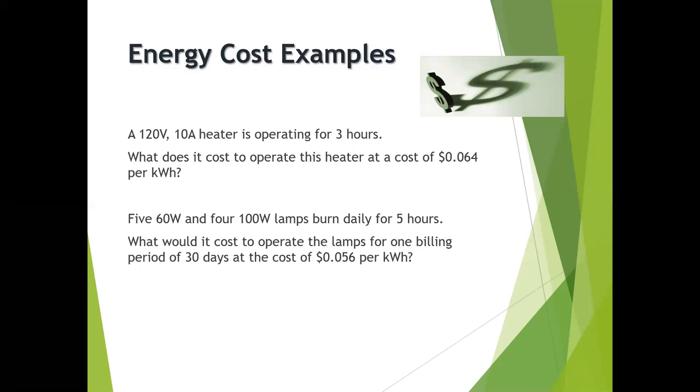In the second example, if we have five 60 watt and four 100 watt lamps and they burn daily for five hours, what is that going to cost? You take your five times 60 is 300 watts, four times 100 is 400 watts. We find our total power by adding those together at 700 watts or 0.7 kilowatts. Remember, knowing our units is important when we're working with these formulas.